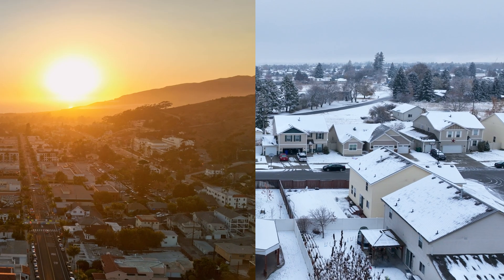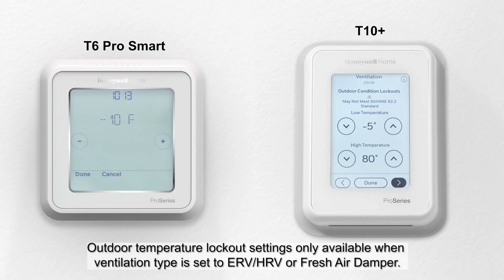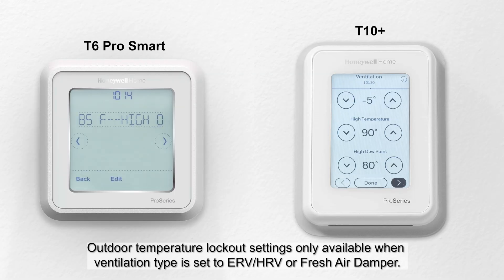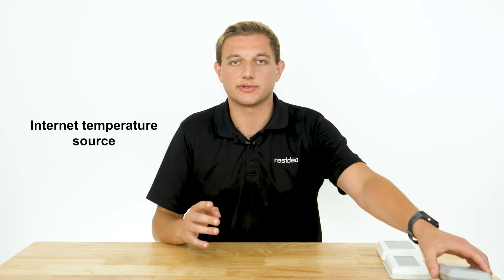To prevent uncomfortable air from entering the home, optional outdoor lockout conditions include locking out ventilation when outdoor temperatures fall below or rise above set temperatures and high dew points. All outdoor temperature lockout settings require an outdoor temperature reading, which can come from a wired or wireless outdoor temperature sensor or an internet temperature source.